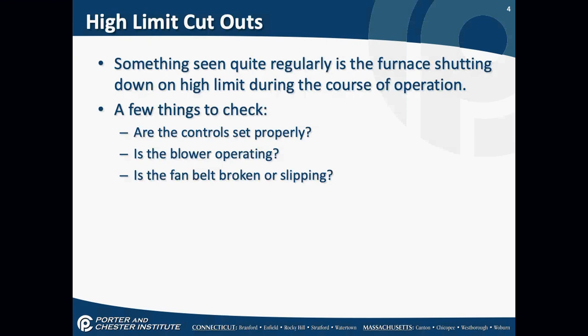What happens if the filter's dirty? Needs to be replaced or cleaned. Yeah, but will my furnace overheat? Oh, yeah. Okay, so if you have a furnace that's bouncing off on the high limit, one of the things to check is make sure the filter's not dirty. What's one other thing you need to check if a furnace is bouncing on high limit, coming on and off based on high limit control? And I'm saying furnace, forced air.